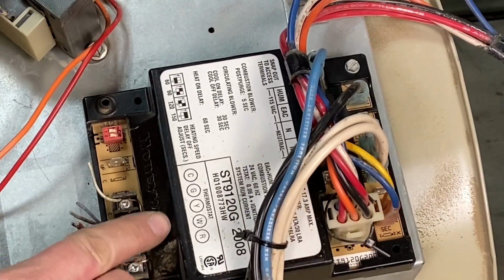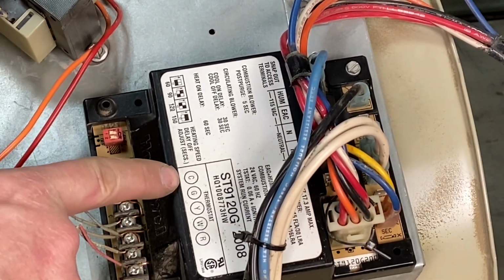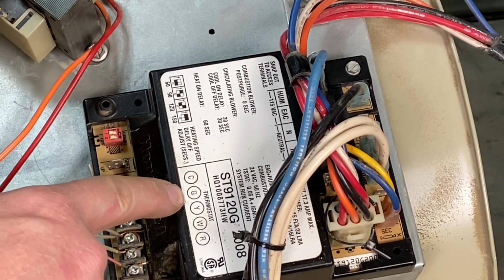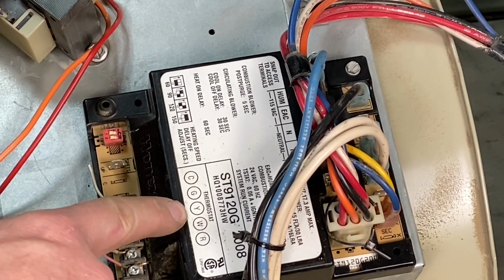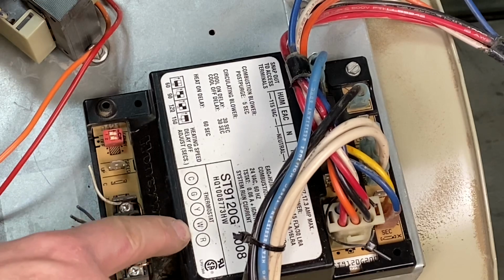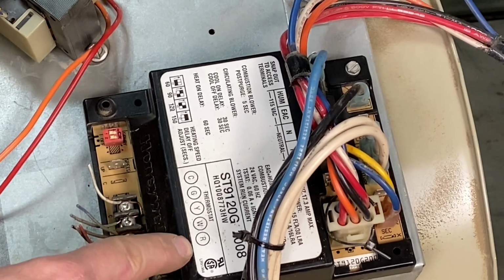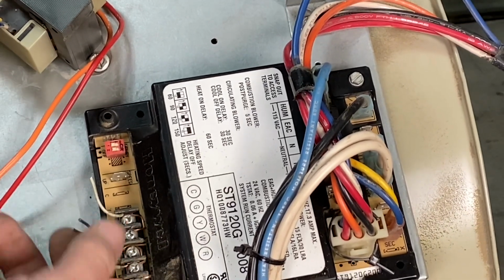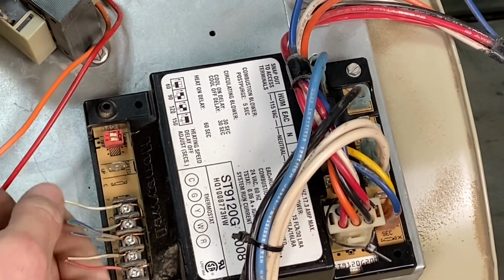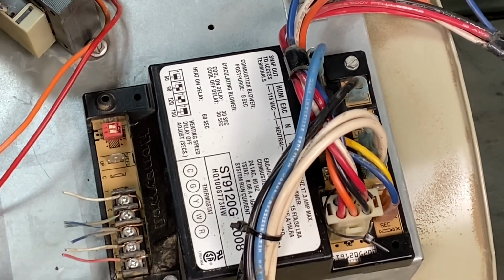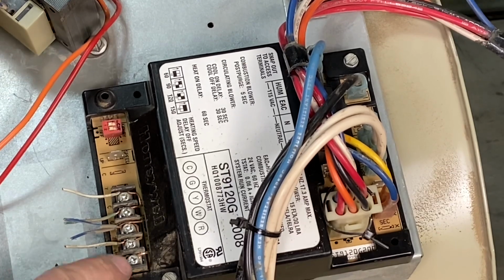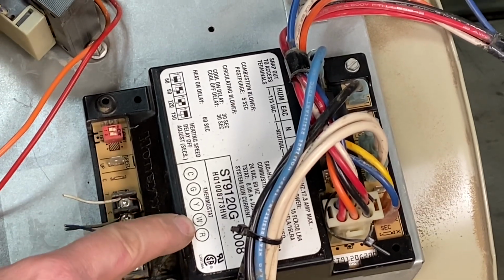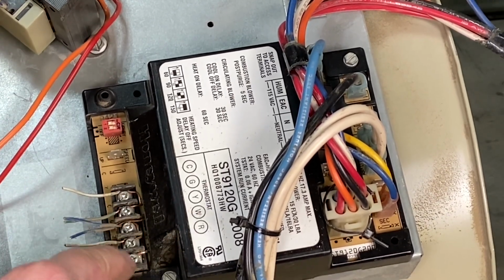The only thing we haven't talked about is these wires. We have C, 24 volt common, G, indoor fan relay, Y, cooling compressor contactor, W, indoor heat, and R, 24 volt power. So here's the thermostat wires that were left. And what's important is to know what the letters mean. So when I have a call for heat, the thermostat connects the R to the W. So when I jumpered it, I put a jumper between R and W.